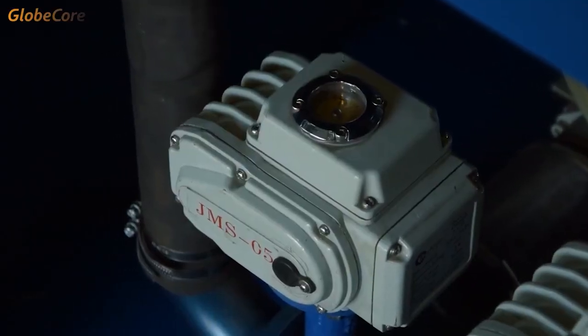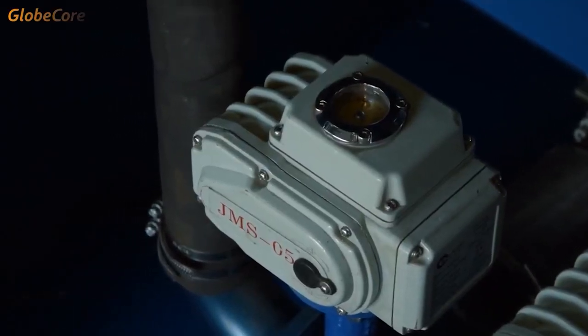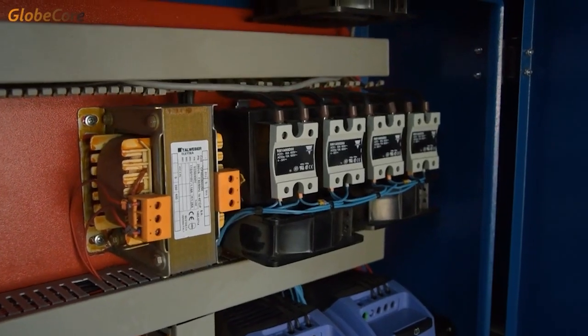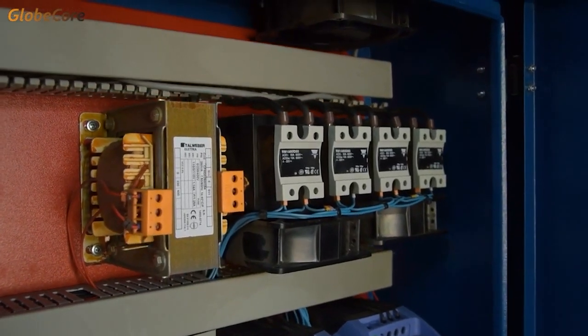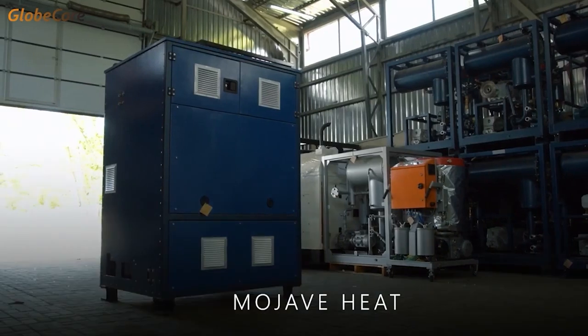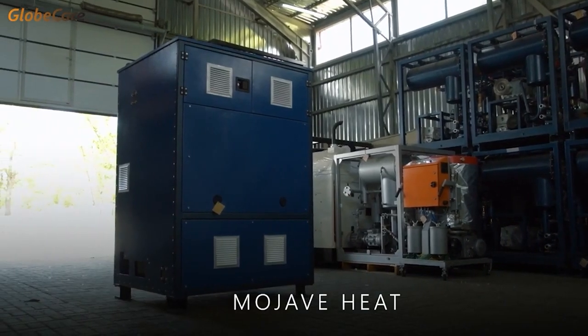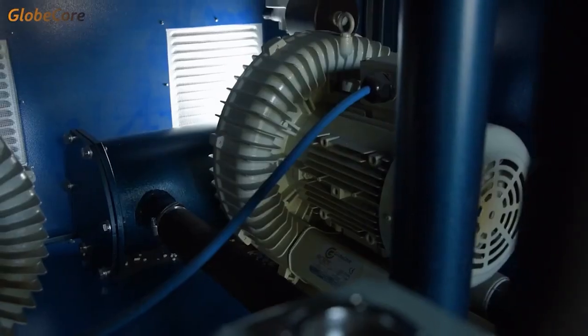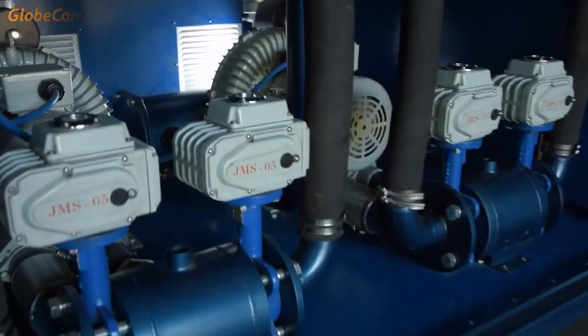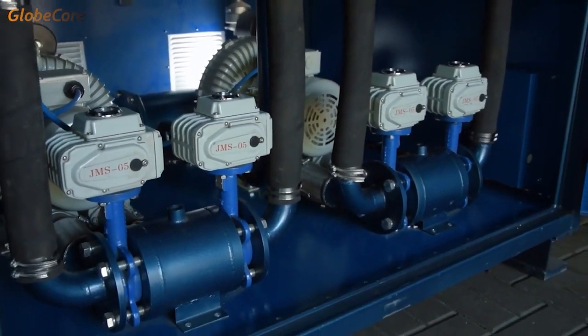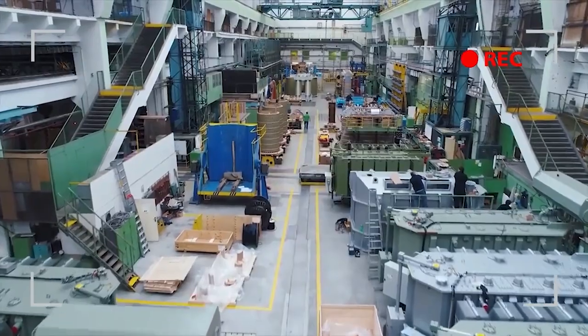The machine ensures a dew point of -50 degrees Celsius, or 223 degrees Kelvin. The dry filtered air from an adsorber and a particulate filter is pumped into the transformer tank, facilitating a flow of fresh air for maintenance personnel inside and preventing atmospheric moisture ingress to the transformer windings.